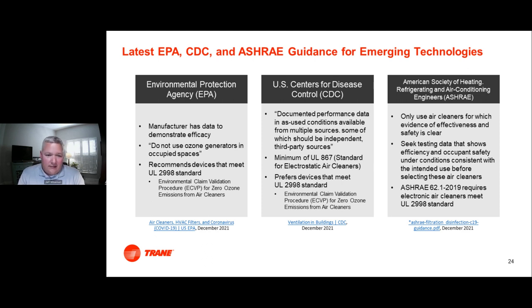UL2998 is claiming zero ozone generation from the device. It allows for 5 parts per billion or less. There is a UL867 they call low ozone. That's 50 parts per billion, but the recommendation is to go for the more stringent UL2998. In addition to UL2998 technology, ASHRAE also wants to see, as I mentioned earlier, third-party independent test data validating any claims being made, and also data that shows the efficiency and safety of the technology under conditions consistent with the intended use.